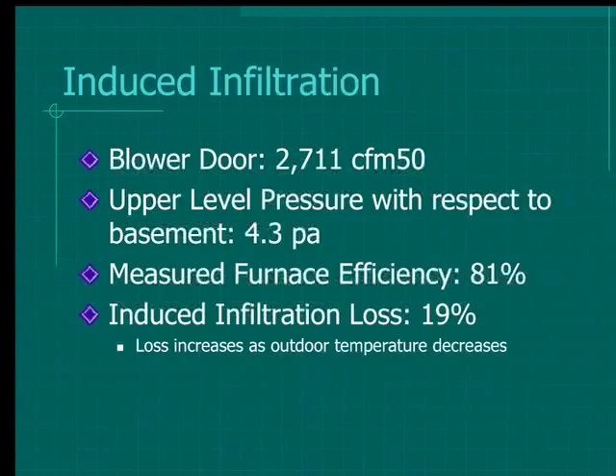And they weren't in balance. We had the returns pulling air out of the basement, sucking the basement negative, and the supplies positively pressurizing the upstairs. One duct system change, one afternoon, took care of this problem. That's about 20% on their gas bill, at least the heating portion, not the hot water heating portion.